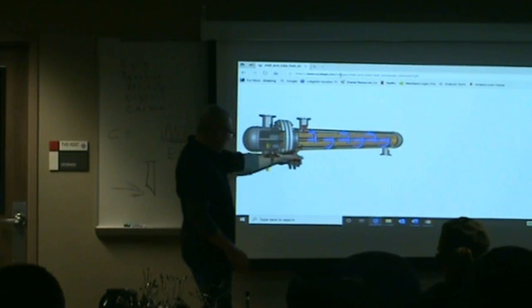Once you start getting these little pinholes in the bundles, you're either going to have process fluid going into the cooling tower water, or cooling tower water going into the process. Either way, it's not good at all.